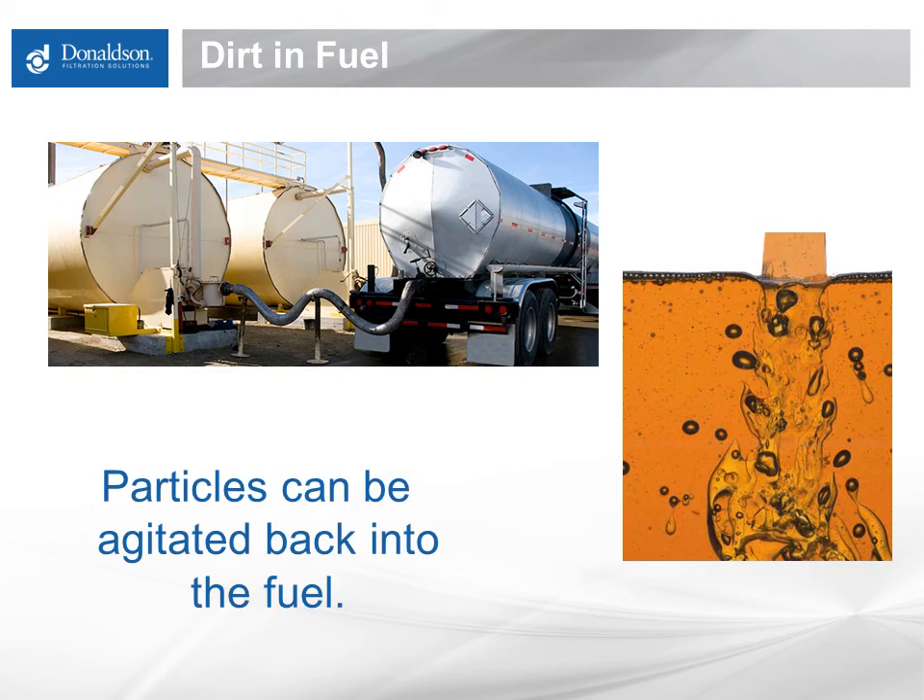As soon as the flow slows down, large things like cars, buildings, trains, etc. are dropped and left when the flow slows down. If that same tank of fuel that had the particulate settle to the bottom is stirred up by driving around or being moved and then pumped from, that debris can be pumped around or transferred and plug filters quickly — think of it as something like a snow globe being shaken up. The same cannot be said for the fine particulate in the fuel, however. By that, we are talking about things less than about 7 microns in size. They remain suspended for very long periods of time.